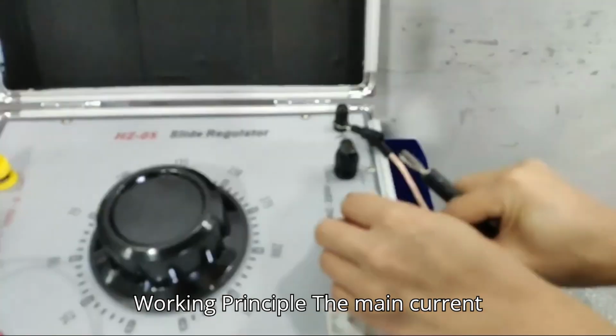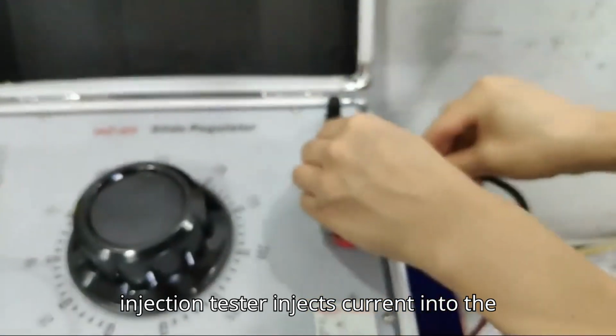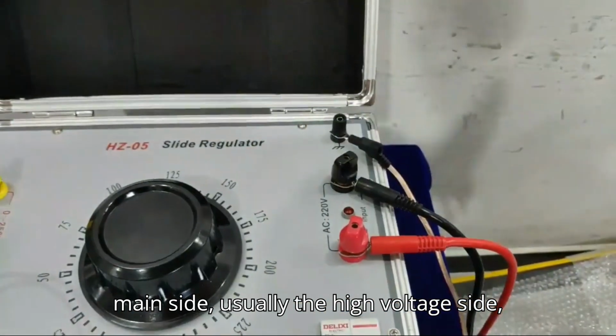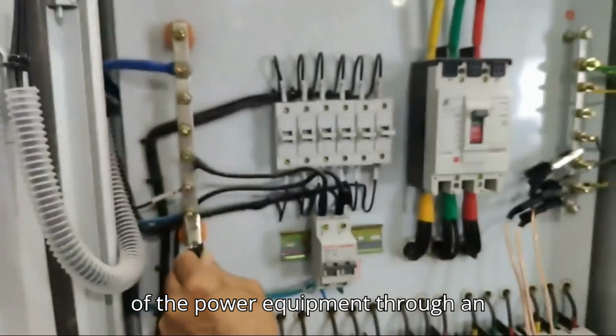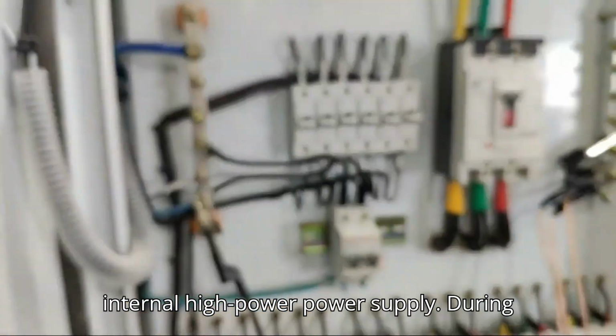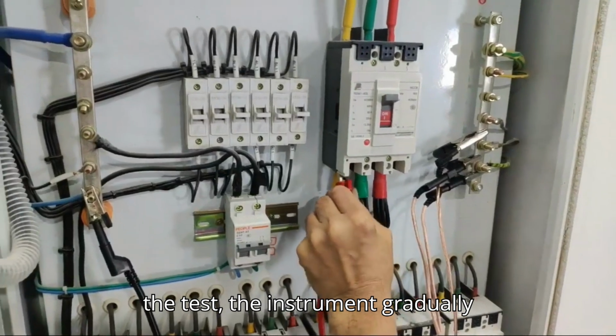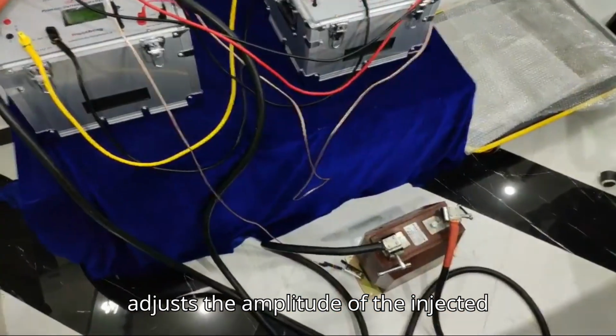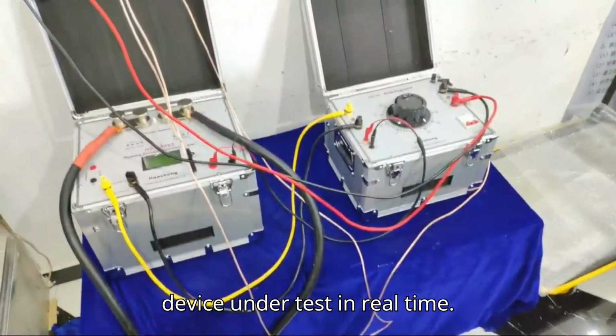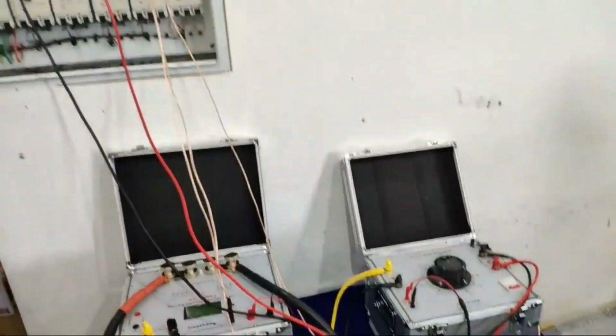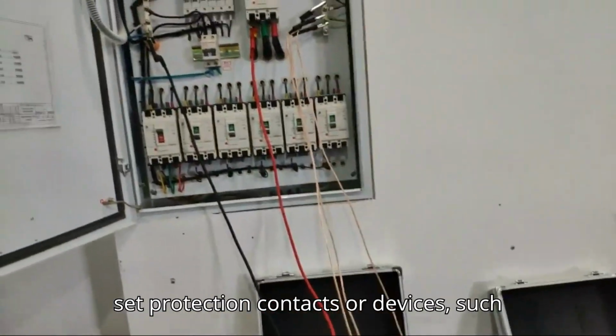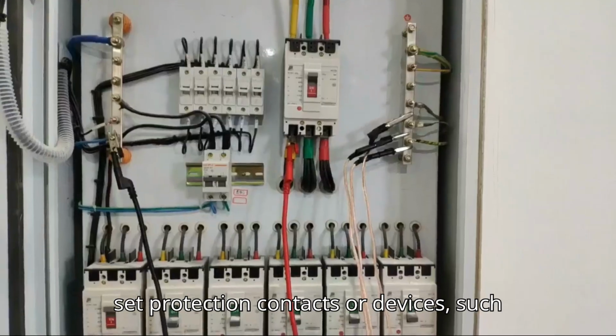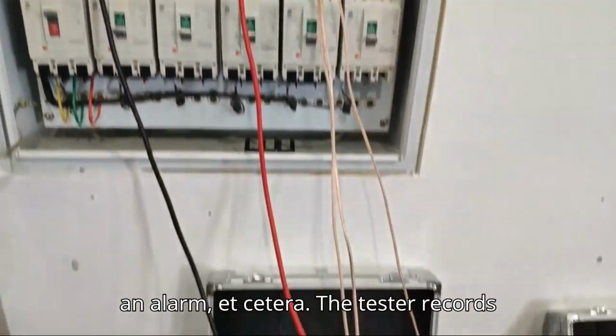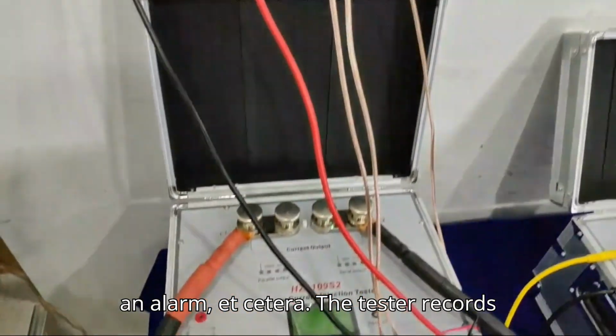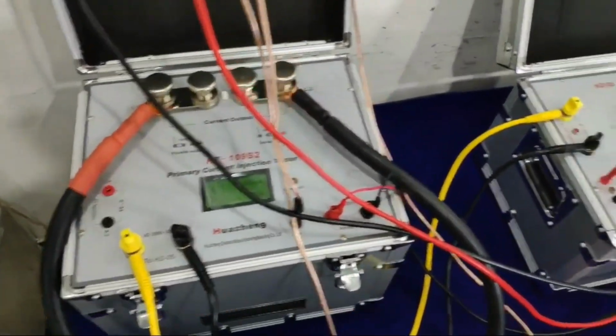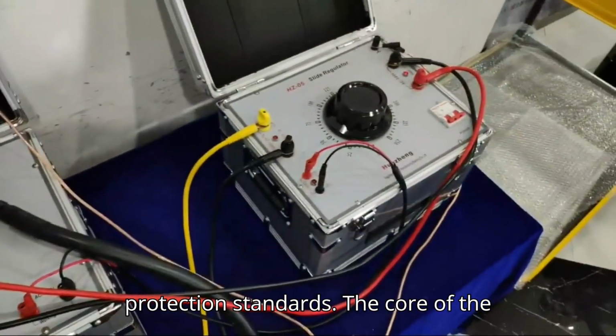Working principle. The main current injection tester injects current into the main side, usually the high voltage side, of the power equipment through an internal high-power power supply. During the test, the instrument gradually adjusts the amplitude of the injected current and monitors the response of the device under test in real time. Usually, the device responds through the set protection contacts or devices, such as disconnecting the current, triggering an alarm, etc. The tester records the response of the protection device and evaluates whether it meets the preset protection standards.